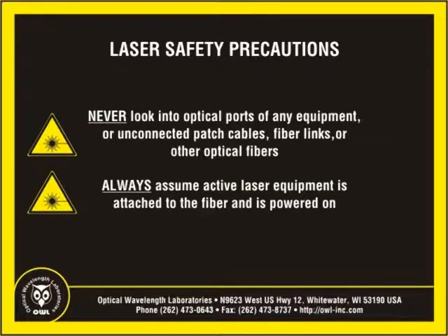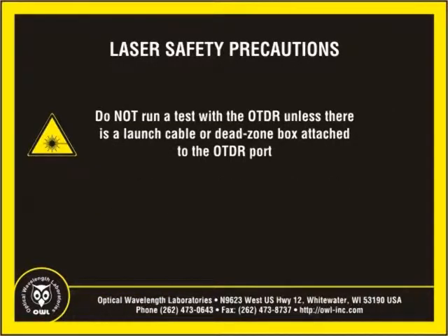Before we begin, there are several safety and operational precautions that need to be addressed. First, never look into the connector port of any fiber optic test or transmission equipment, patch cable, fiber link, or other installed fiber. For your safety, always assume that active laser equipment is attached to optical fibers and is powered on. Second, do not run a test with the OTDR unless there is a launch cable or dead zone box attached to the OTDR port.